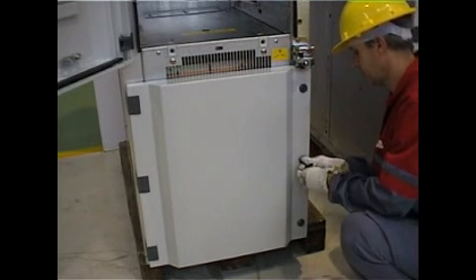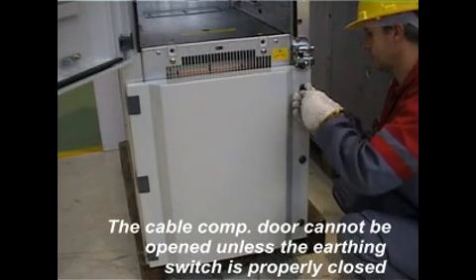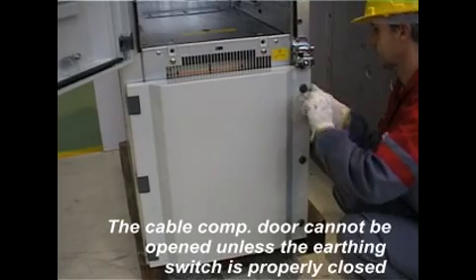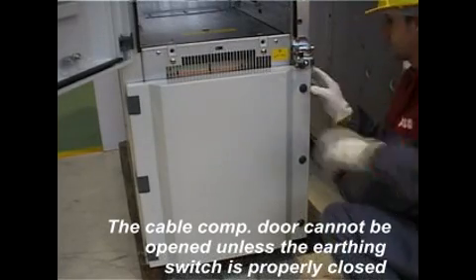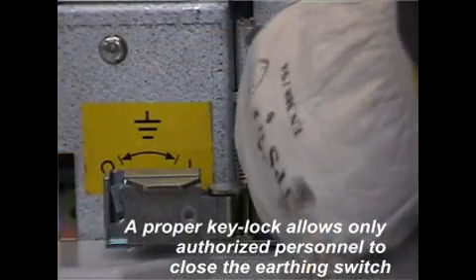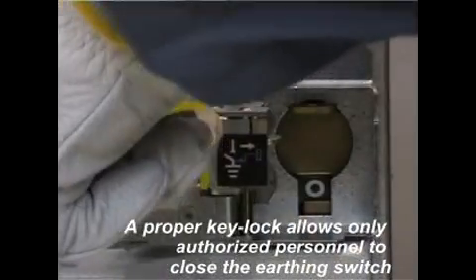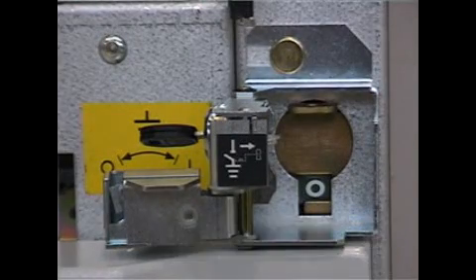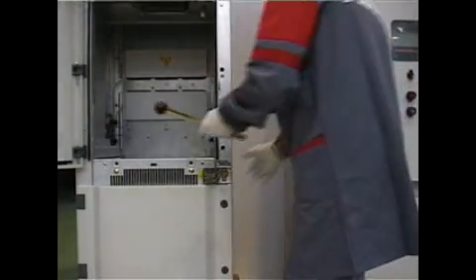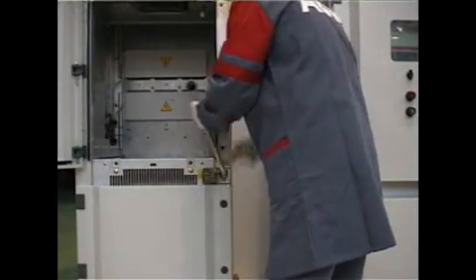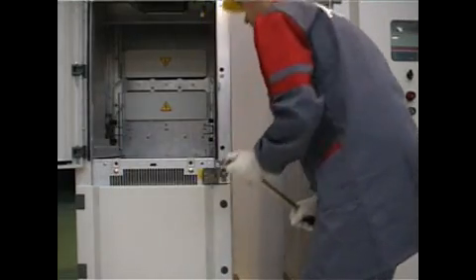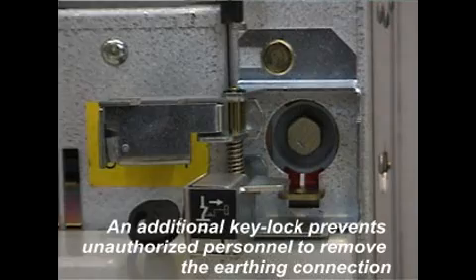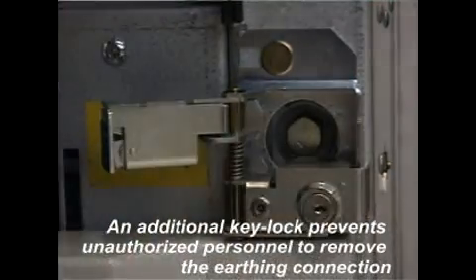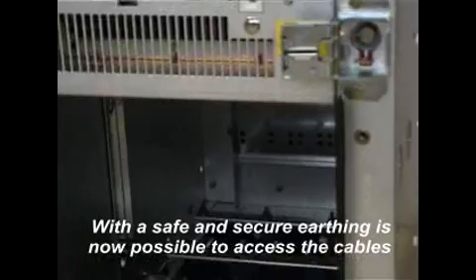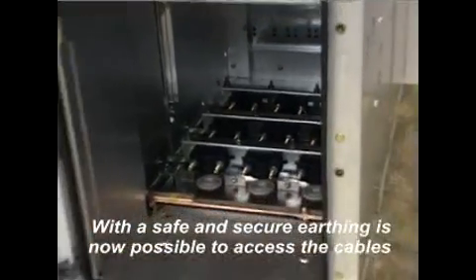We can go ahead and try to open the cable compartment in order to check the status of the terminals, but this operation is prevented by a proper interlock which requires the earthing switch to be in closed position. To earth the cable side, we insert the key to get access to the proper shaft, then we insert the lever and we operate the earthing switch. Now that the earthing switch is closed to ground, we can operate the key lock and remove the key to make sure nobody will operate it while we work on the cables. When the earthing switch is closed, we can open the cable compartment door to get access to the cables.